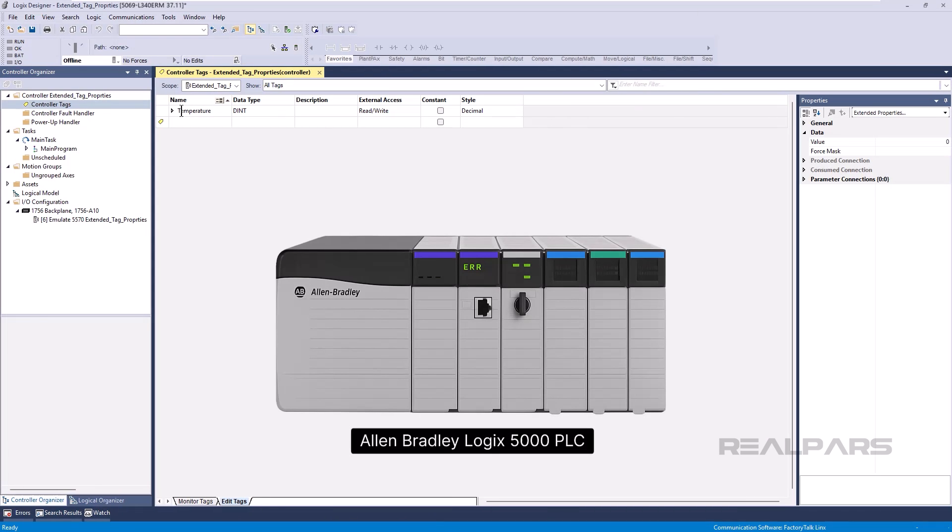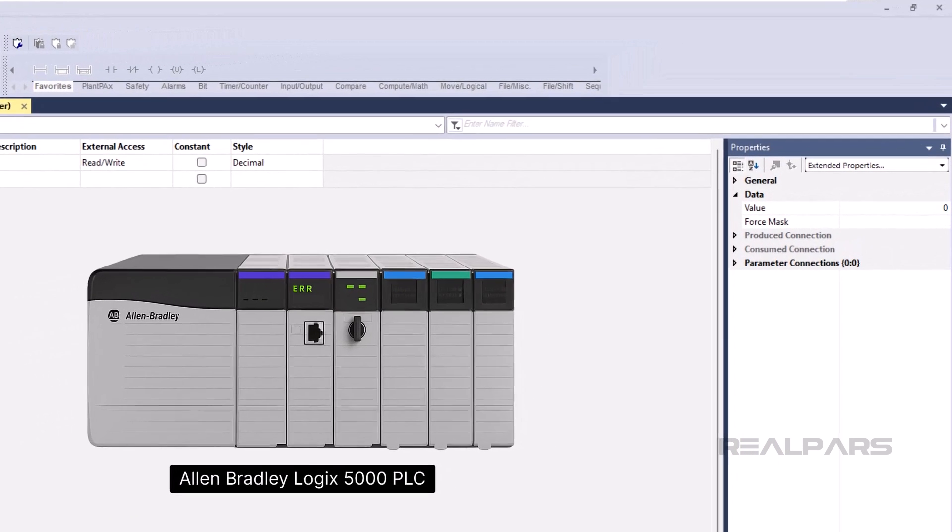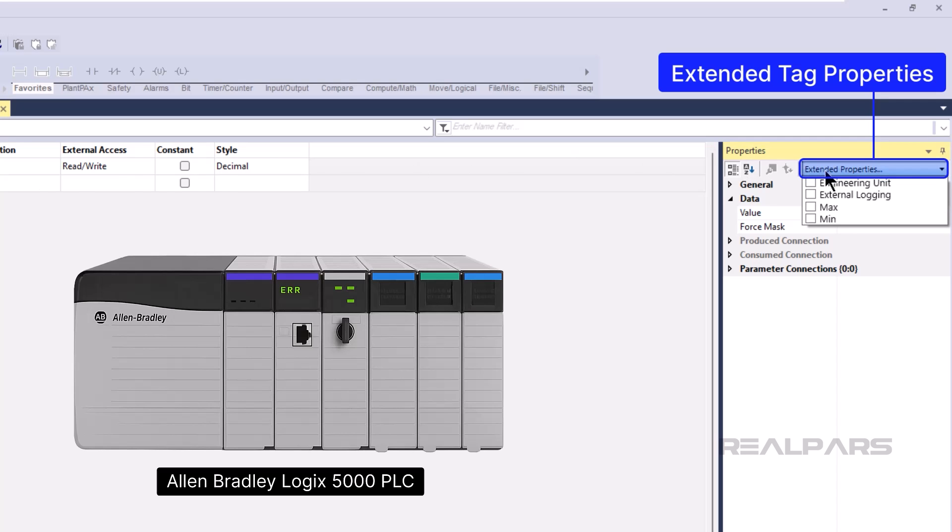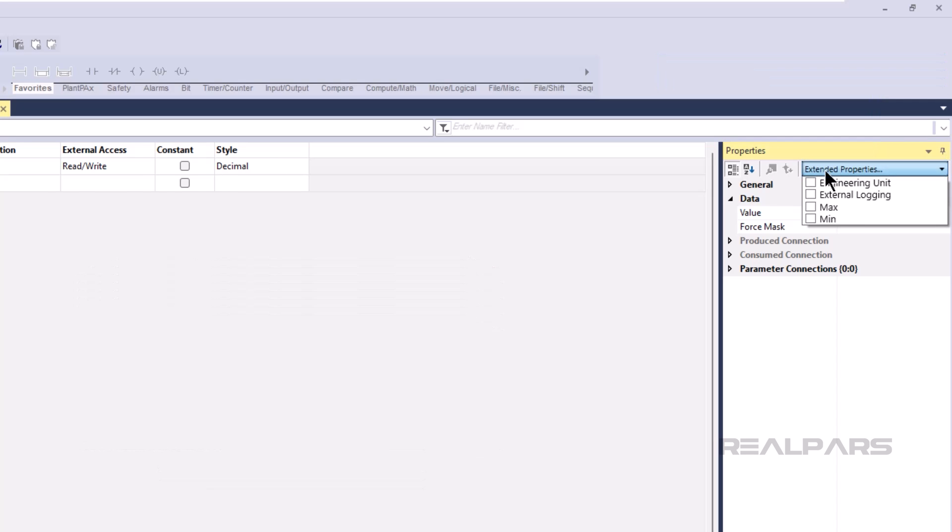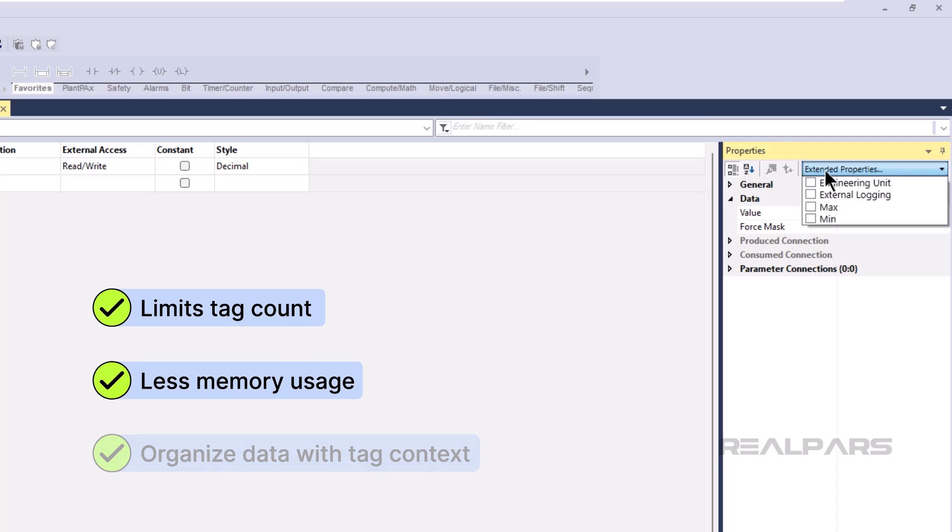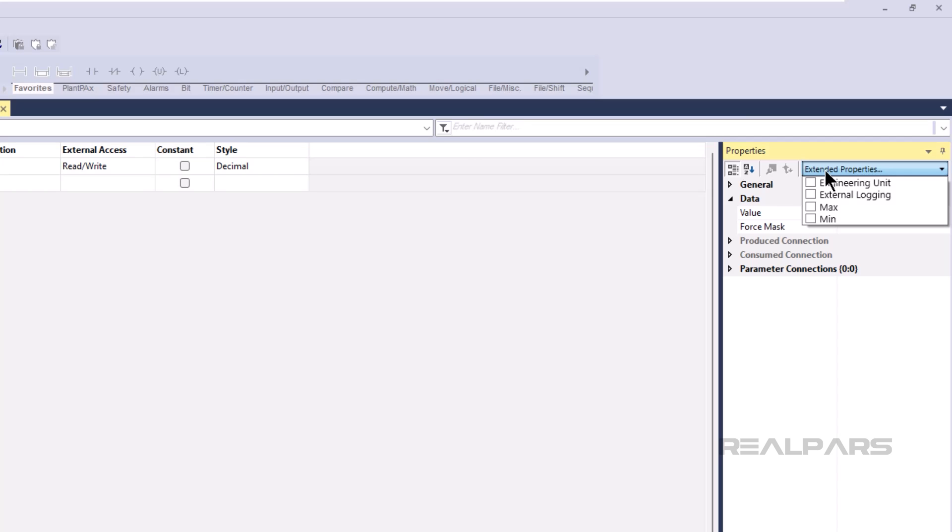Allen-Bradley Logix 5000 PLCs have a feature called Extended Tag Properties that lets you add extra information to each tag. This helps to limit the amount of tags that have to be declared and the amount of memory used by the tags. It also helps to organize data by adding context to tags.